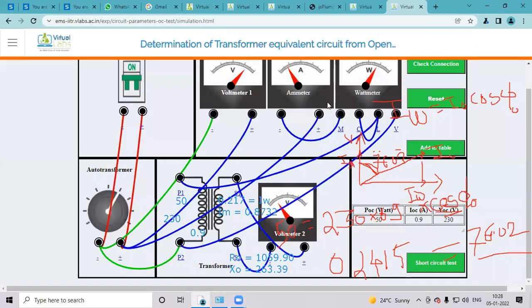Did everyone understand the connection for the OC-SC test? Yes, sir. Okay, both tests, OC and SC - there is a mistake in that diagram. Always the ammeter can be connected in series to measure the current, and always the voltmeter can be connected in parallel. But in the theory diagram there is a mistake between voltmeter and ammeter, so don't make this mistake. If you connect the ammeter in parallel and voltmeter in series, if the voltmeter is connected in series and ammeter in parallel, then this equipment may burn.